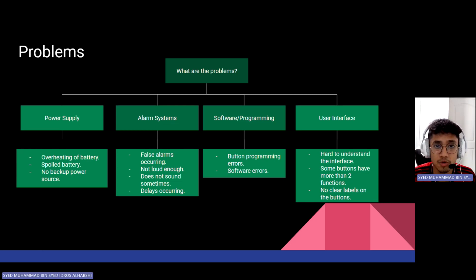For example, if you're on a screen where you have not decided what delivery rate to set yet, the arrow buttons could be to go up the menu or go down the menu. However, when you're on the delivery set rate, you can actually adjust the delivery rate using those arrows at the same time. For some users, this may actually be problematic as they cannot understand how to do it and they might not be able to use this infusion pump effectively, which may in turn affect the patients negatively.